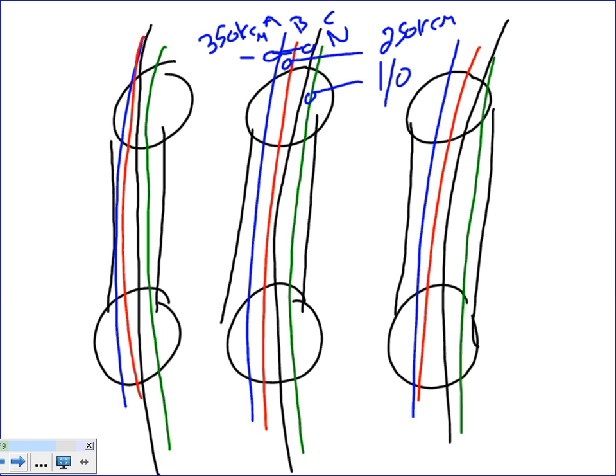If you pull all your neutral in one conduit, all your phase A in one conduit, all your phase B in one conduit, all your phase C in one conduit, that's okay if they're PVC only, coming from the bottom with no holes. If you do that, you can come up with a much smaller neutral size.